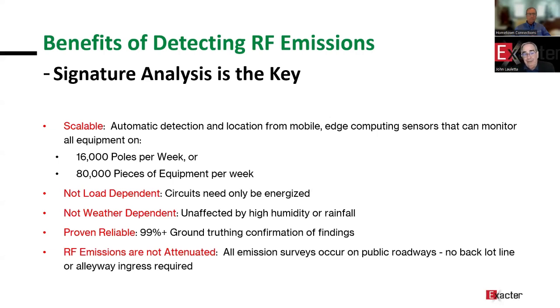Now, there's a real benefit to using these RF emissions over things like thermal emissions, or some people use corona. Of course, you can't typically use that in distribution because there's no corona at lower voltages. But our technique is very scalable. One sensor on a garbage truck can look at 16,000 poles a week and gather information on up to 80,000 pieces of equipment, each one of which, if it fails, will cause an outage. Our system is not load dependent.